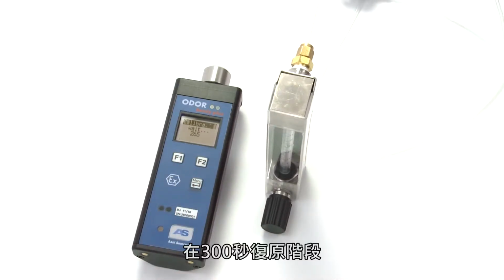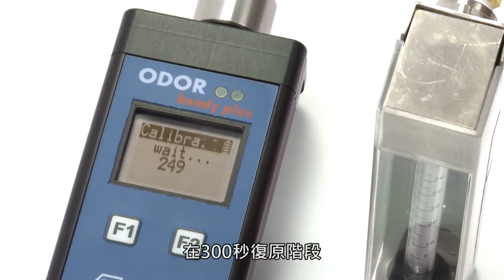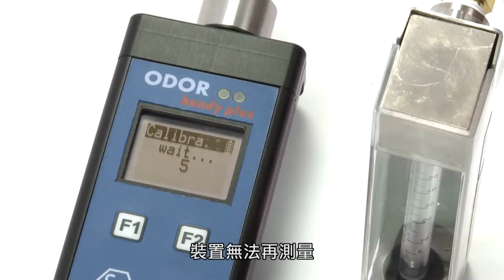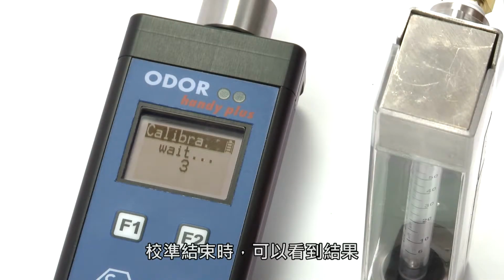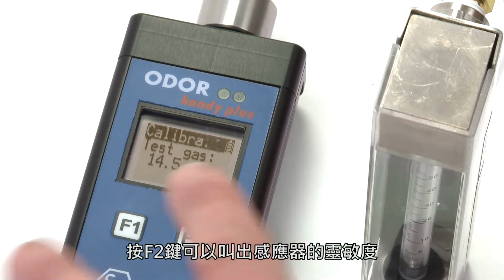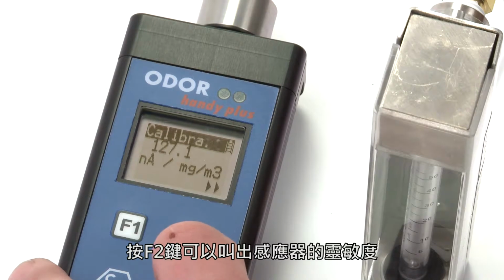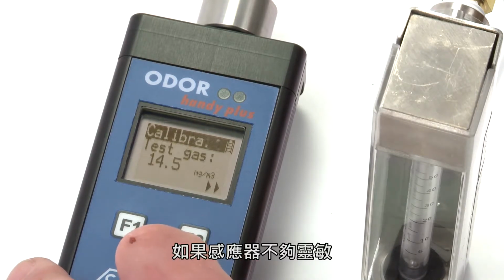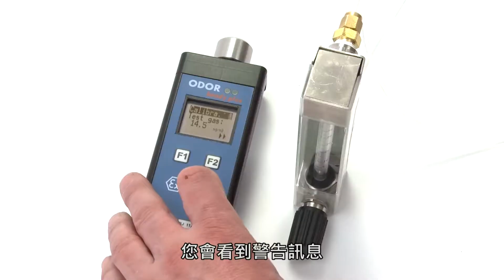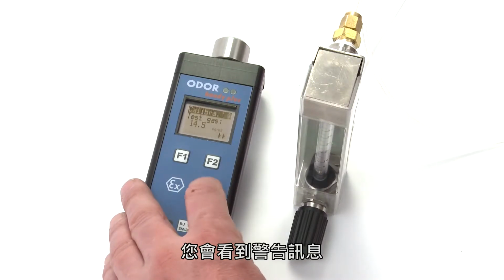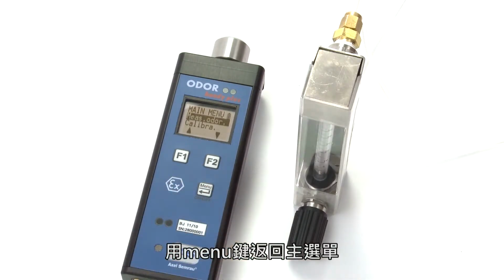During the regeneration phase of 300 seconds, the device will be blocked for further measurements. At the end of calibration, you will see the results and can retrieve the sensitivity of the sensor via the F2 key. If the sensor is no longer sensitive enough, you will get a warning message to this effect. Use the menu button to return to the main menu.